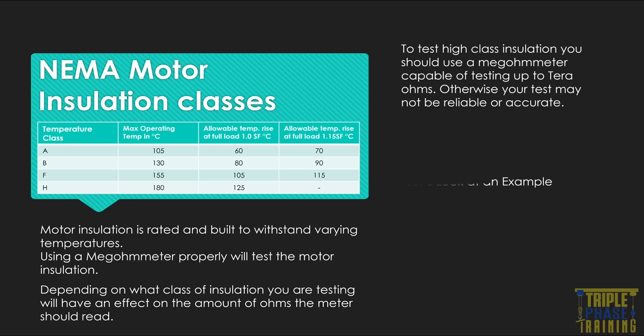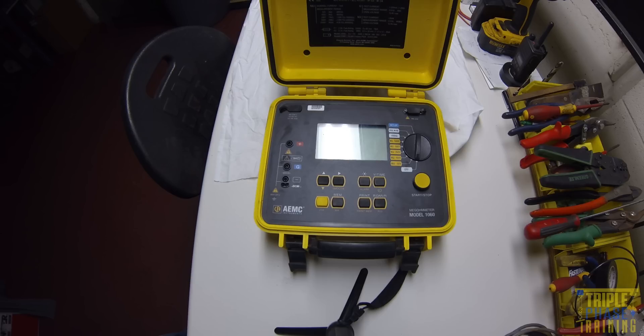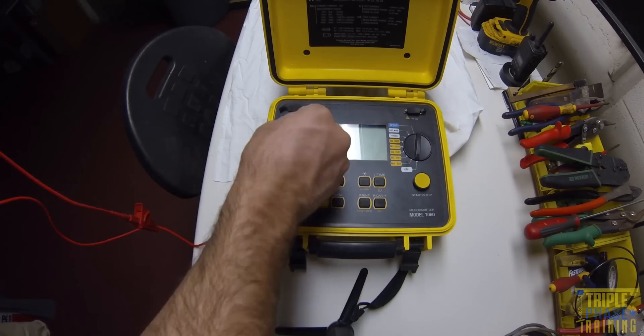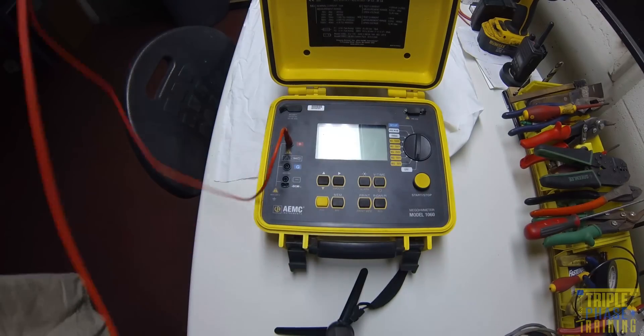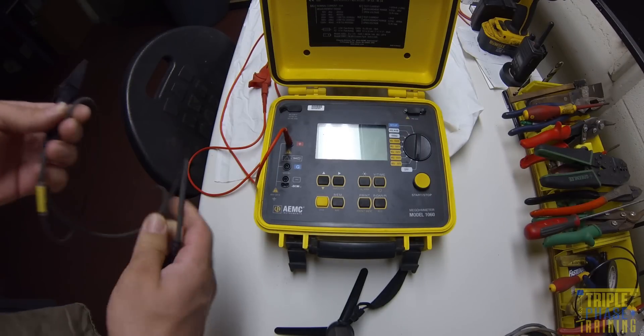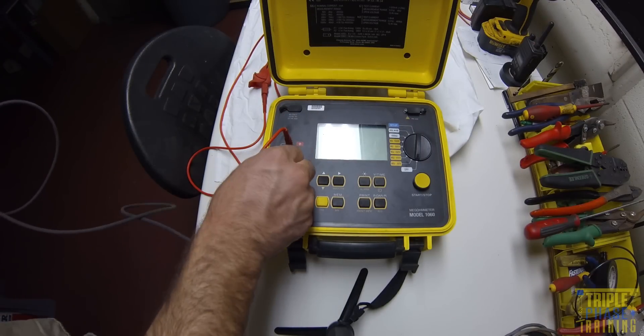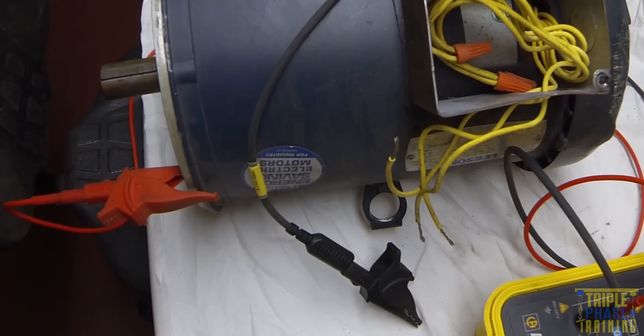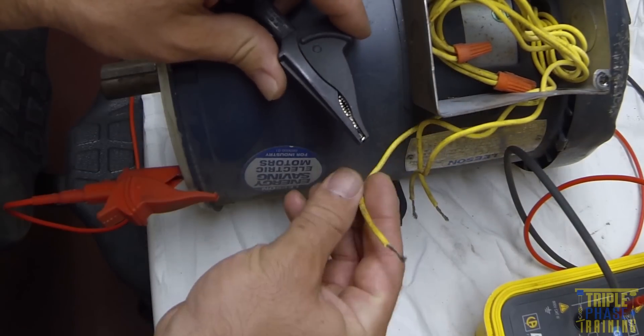Let's look at an example. The megohmmeter we are using is an AEMC model 1060. Be sure to read all the instructions and precautions before using your meter. Connect the appropriate leads to the meter. Then, following the instructions provided by the manufacturer, make the correct connection to the motor casing and motor lead. In this test, the positive lead is connected to the casing and the negative lead is connected to the motor lead.